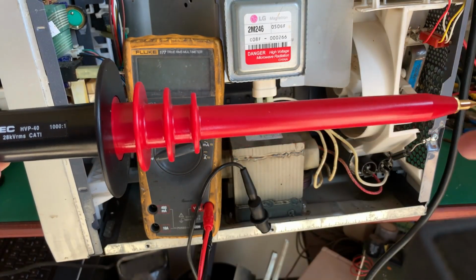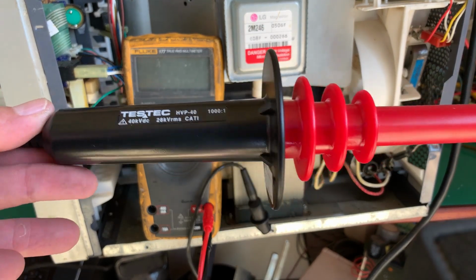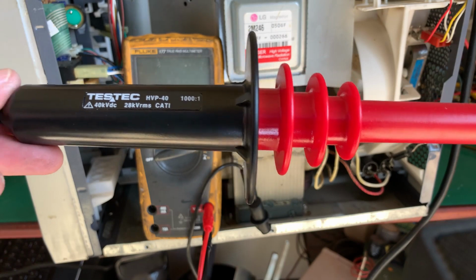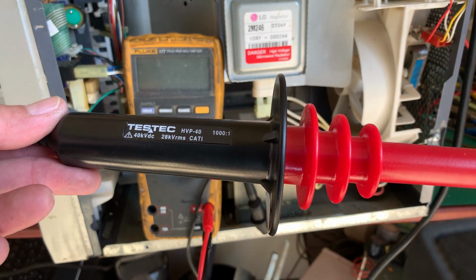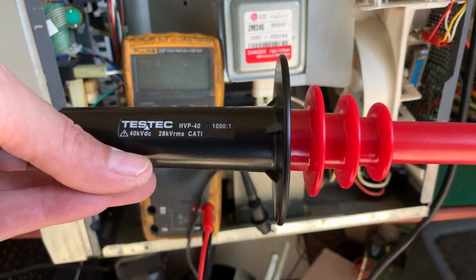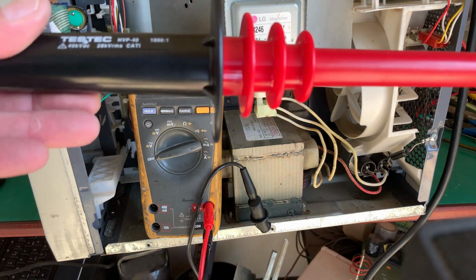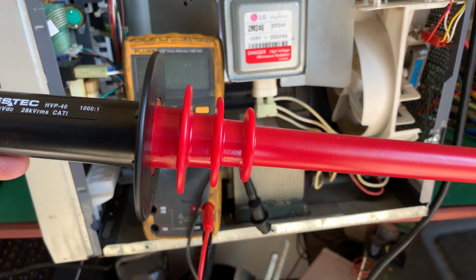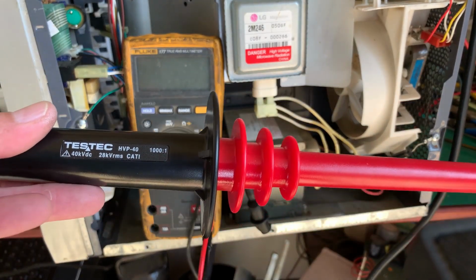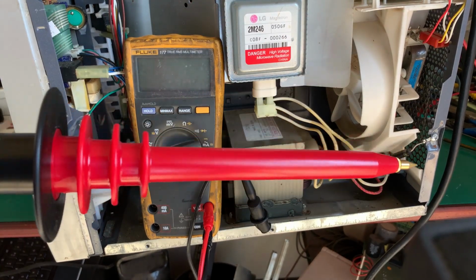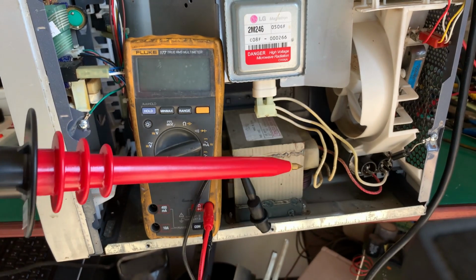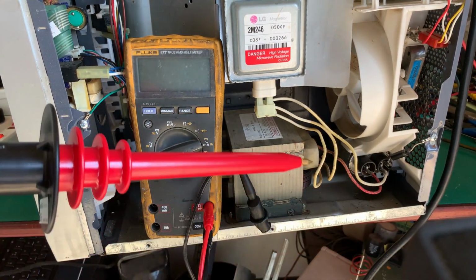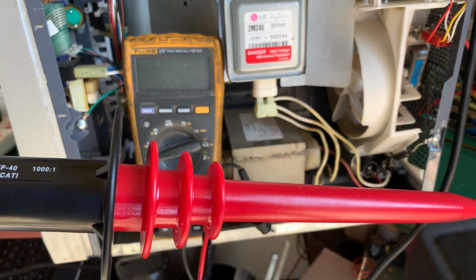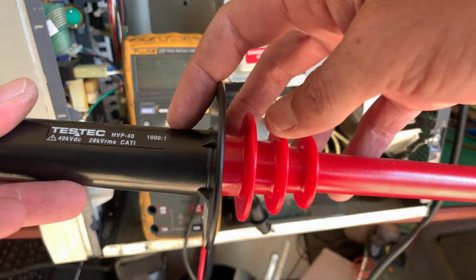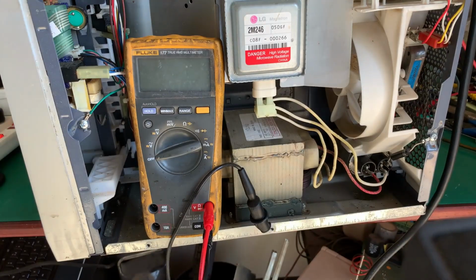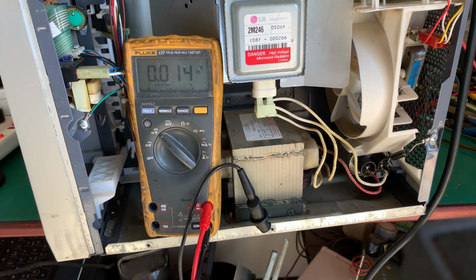Right, we're back, and as you can see I've got this nasty looking device here. It is a high voltage probe. It can measure up to 40,000 volt DC or 28,000 volt AC RMS. Notice it is a Cat 1 instrument, so you really do not want to be plugging this thing anywhere where you don't have an isolation transformer to get you away from your power provider. So for something like this, to measure in here, it's fine. I'm behind the mains high voltage transformer here. That's good. It's actually isolating us, and of particular interest, it's a 1000 to 1. So whatever I'm going to read on the multimeter, we would multiply that by 1000.